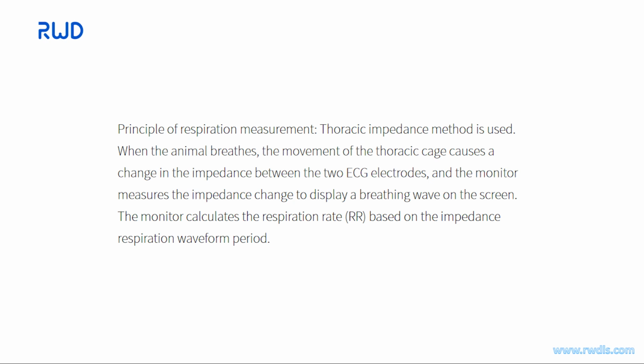Principle of respiration measurement: the thoracic impedance method is used when the animal breathes. The movement of the thoracic cage causes a change in the impedance between the two ECG electrodes, and the monitor measures the impedance change to display a breathing wave on the screen. The monitor calculates the respiration rate, RR, based on the impedance respiration waveform period.